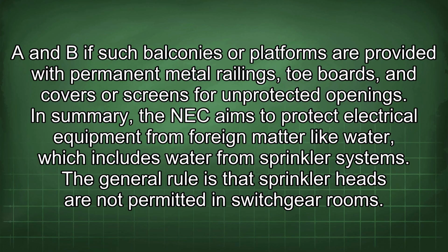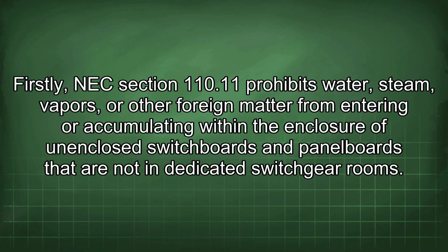In summary, the NEC aims to protect electrical equipment from foreign matter like water, which includes water from sprinkler systems. The general rule is that sprinkler heads are not permitted in switchgear rooms. Firstly, NEC Section 110.11 prohibits water, steam, vapors, or other foreign matter from entering or accumulating within the enclosure of unenclosed switchboards and panel boards that are not in dedicated switchgear rooms.